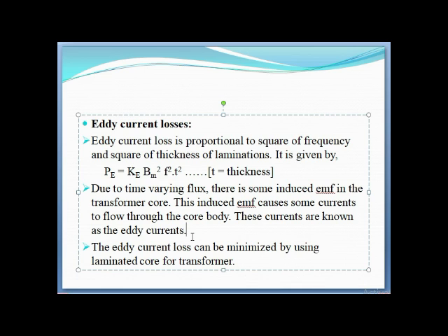To minimize eddy current losses, a laminated core is used. Instead of making the transformer core a single body, it is made of a number of thin plates. Each plate is laminated with resistive material so that current cannot flow from plate to plate. This way, only the magnetic flux is transferred through the core, not eddy currents.